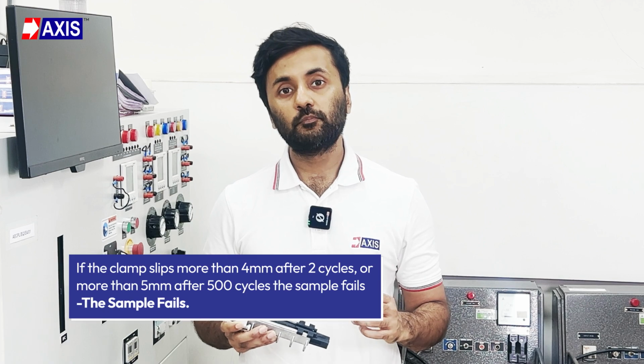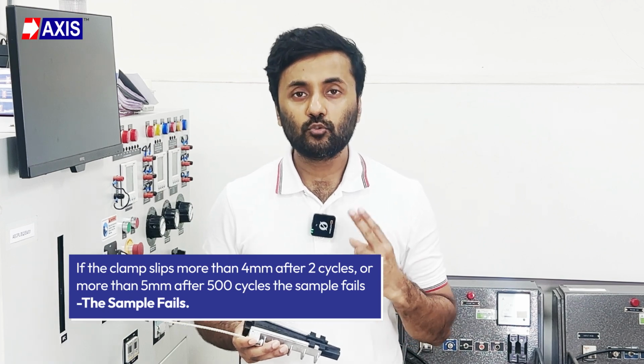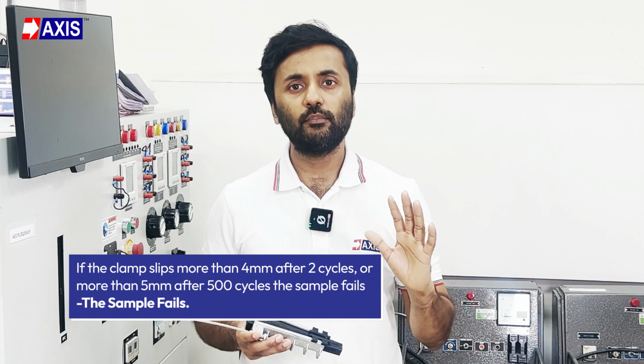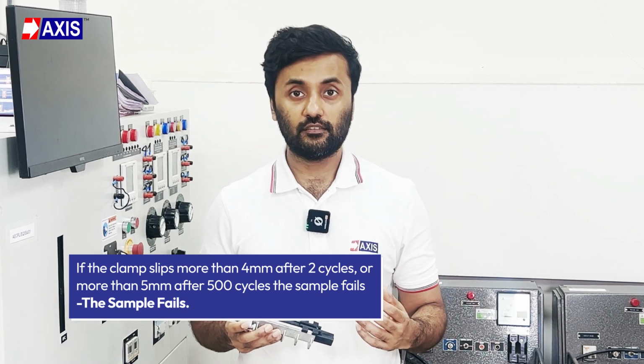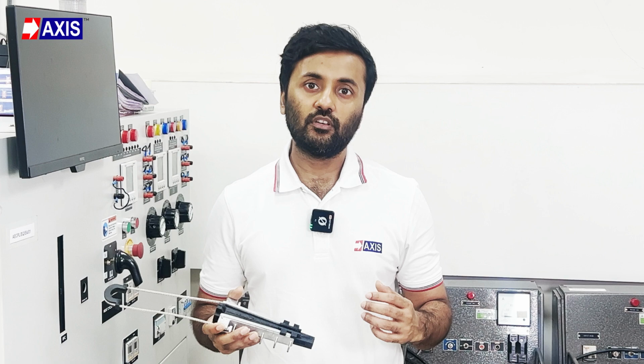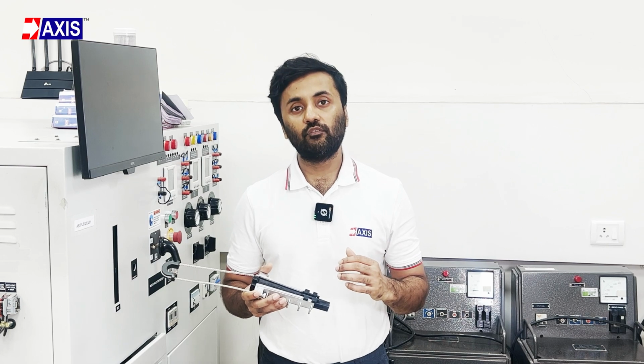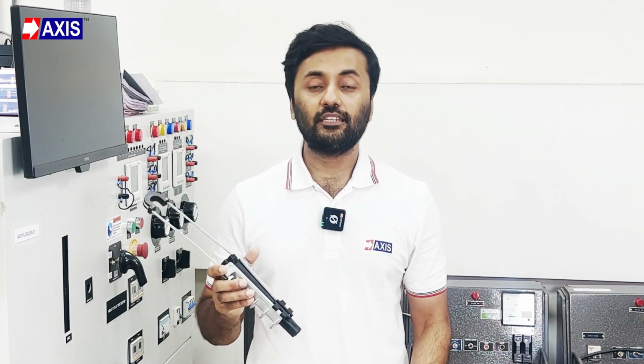If the clamp slips more than 4 mm after 2 cycles or more than 5 mm after 500 cycles, then the sample fails. Any crack, deformation, or insulation failure also leads to failure. After 500 cycles, the clamp must also pass the dielectric voltage test. I hope you now have a clear understanding of how anchoring clamps work and the rigorous quality tests they undergo.